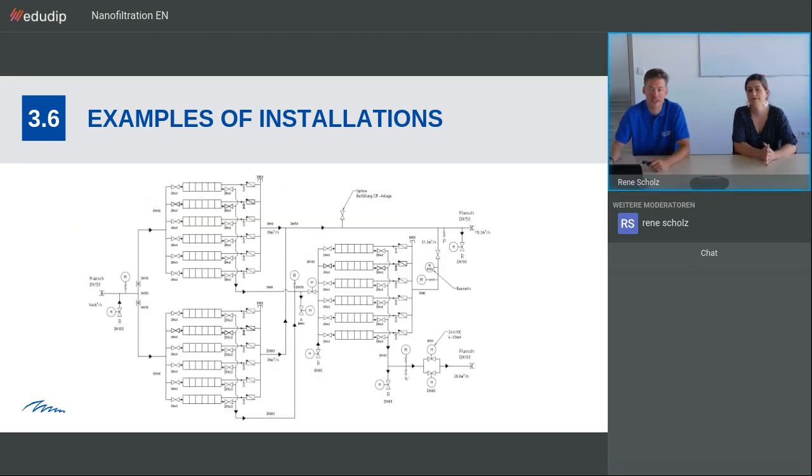All right, in this picture you see the schematics. It looks quite big, but this is just to give you an idea of what we did there. We have the reverse osmosis stages on those 2 parts, and then the stages with the nano membranes. We are not draining or recycling the permeate of the nano stage as we do with the RO systems. We are actually blending the produced permeate with the nano permeate. So it's a bit different from the standard application, but also an interesting solution for the design.